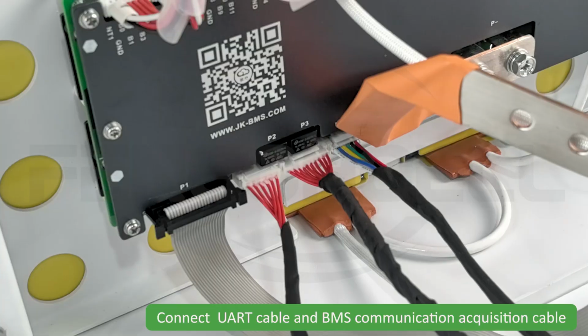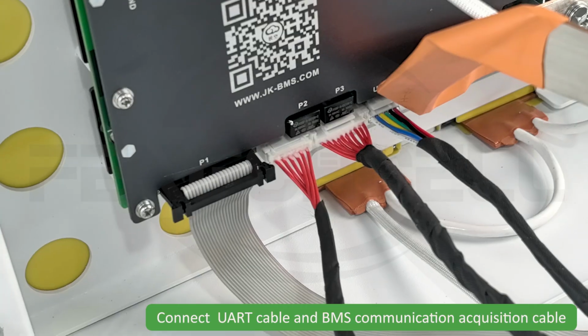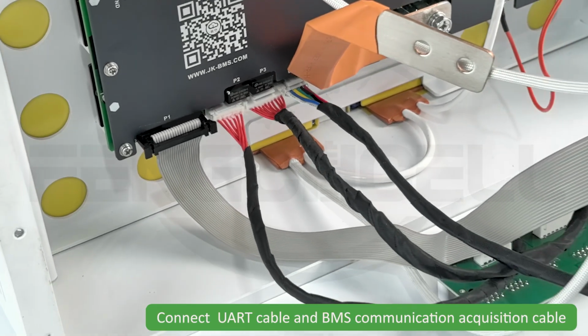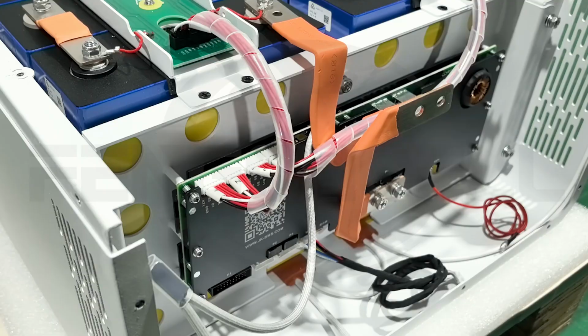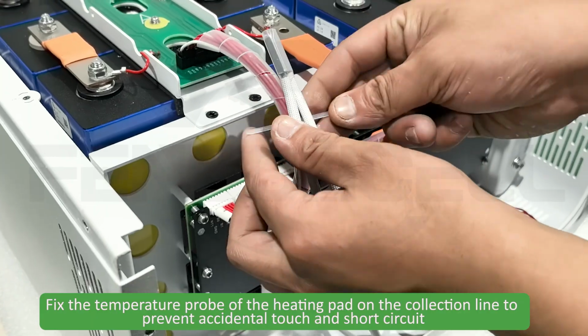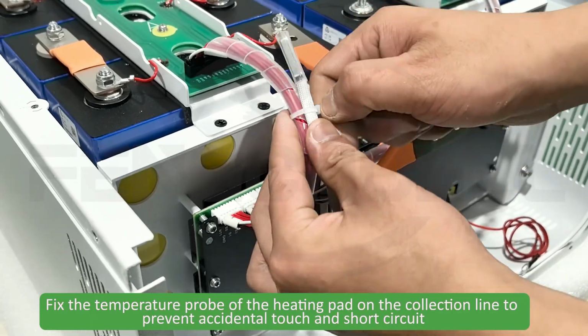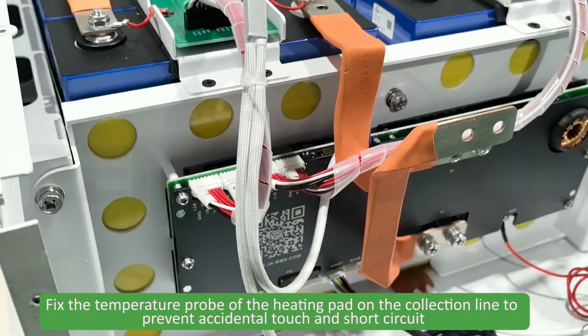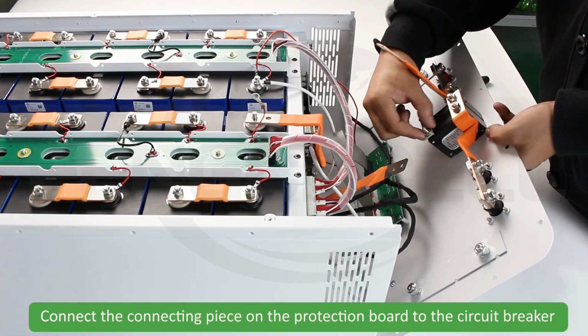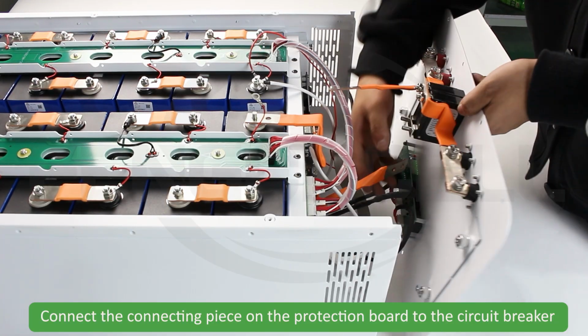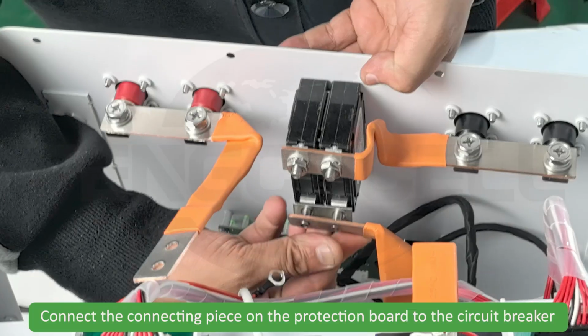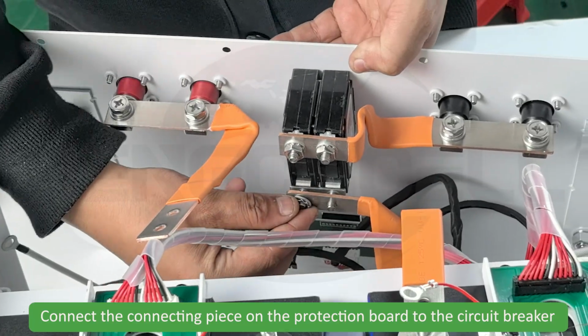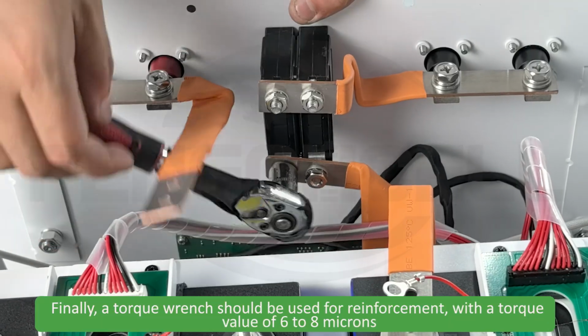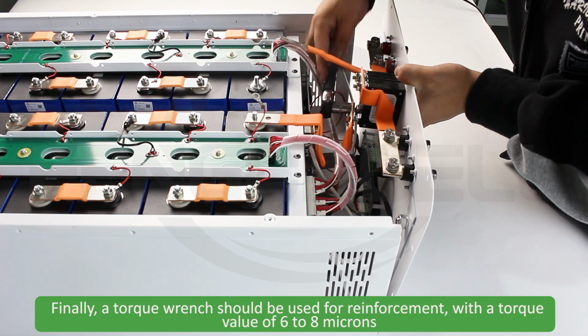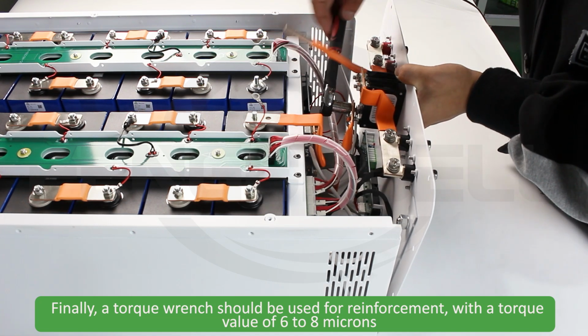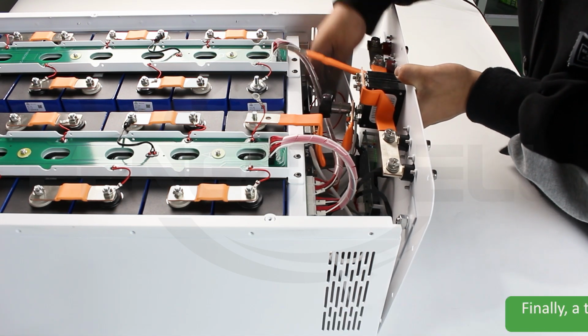Connect the UART cable and the BMS communication acquisition cable. Fix the temperature probe of the heating pad on the collection line to prevent accidental touch and short circuit. Connect the connecting piece on the protection board to the circuit breaker. Finally, a torque wrench should be used for reinforcement with a torque value of 6 to 8 Nm.